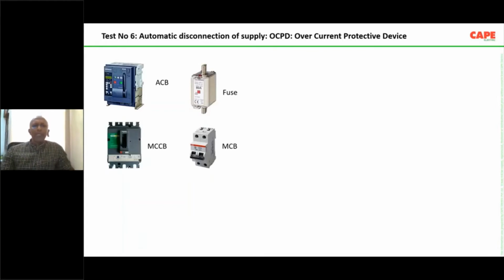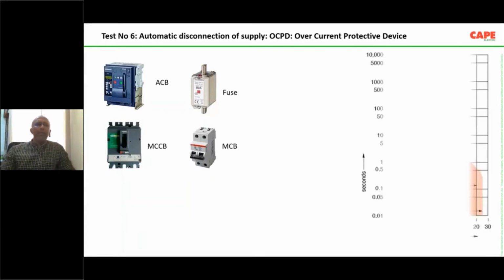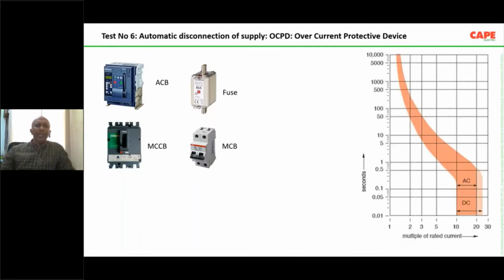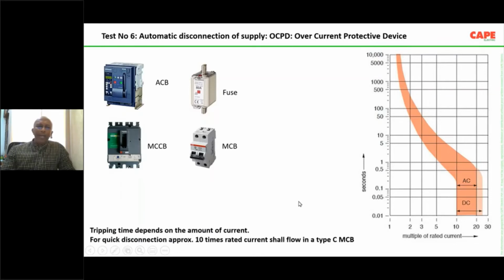In case of a problem in a circuit, the supply should trip, and you have devices such as fuse, MCB, MCCB, ACB, and these devices are called OCPD, overcurrent protective device. And most of these devices have a tripping curve, as in this particular picture. On the x-axis, you can see 1, 2, 3, 4 up to 30. This is the multiples of rated current, and on the y-axis, the tripping time in seconds. Say, for example, you have a type C MCB.